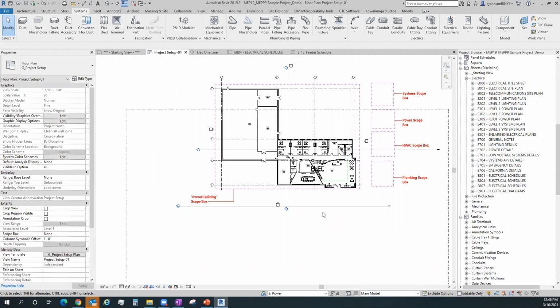So that would be one distraction on my end to say, if I have to have a OneLine before I have a building to draw in, then the system doesn't necessarily work all that well, because I'd really like to place the real equipment in the real room one time and then draw my OneLine off of that. So whether you used a Visio or something like that to kind of get things down in your head, or a SketchUp or Format or something like that to make a mock OneLine or even CAD initially, that would be one way to get around that. And then later come in and do a real OneLine with real equipment in its real physical locations. After you think you got it all in the correct places, then that becomes easier to use this type of a system.